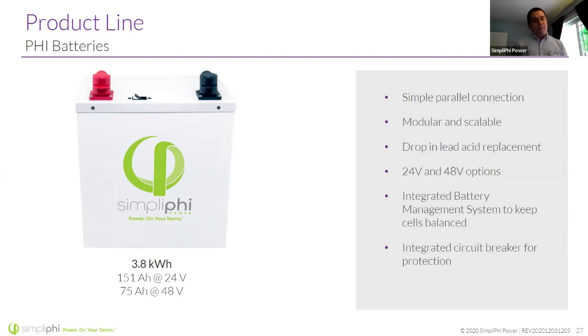Now, the battery management system does not substitute for a poorly designed system, but it is going to help you if something out of the ordinary happens. If your generator runs out of gas and you're away, approaching a low state of charge, the battery management system can open up and prevent that battery from over-discharging to too low of a voltage. And like I said, it's got a breaker.